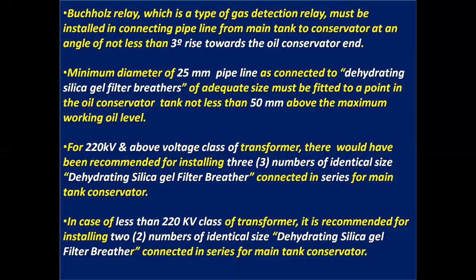For 220 kV and above voltage class of transformer, there would have been recommended for installing 3 numbers of identical size dehydrating silica gel filter breather connected in series for main tank conservator. In case of less than 220 kV class of transformer, it is recommended for installing 2 numbers of identical size dehydrating silica gel filter breather connected in series for main tank conservator.